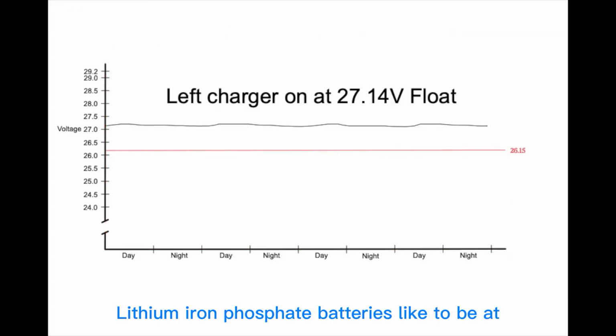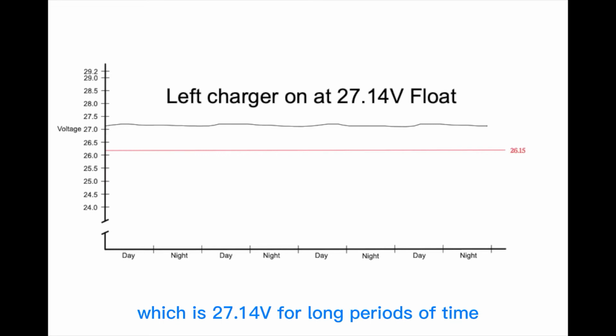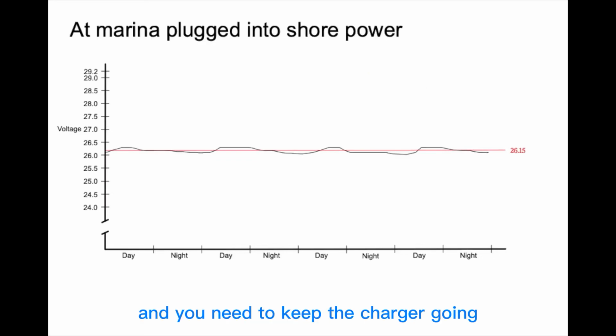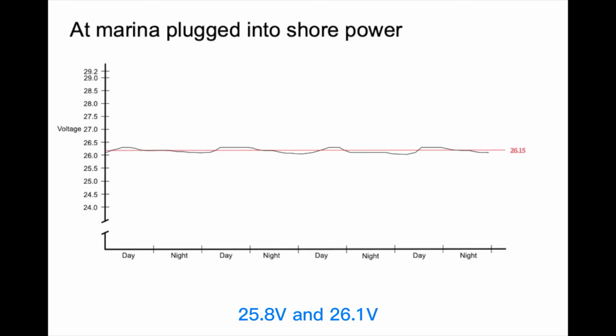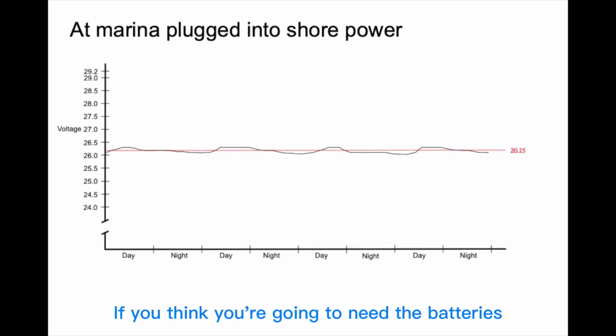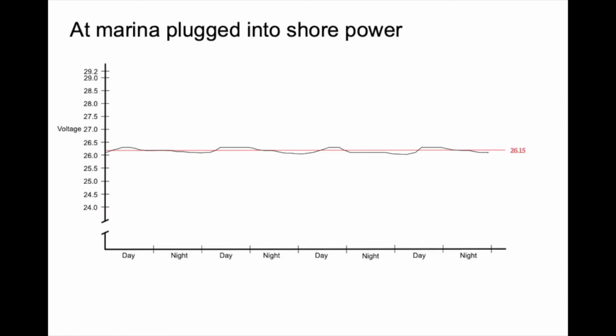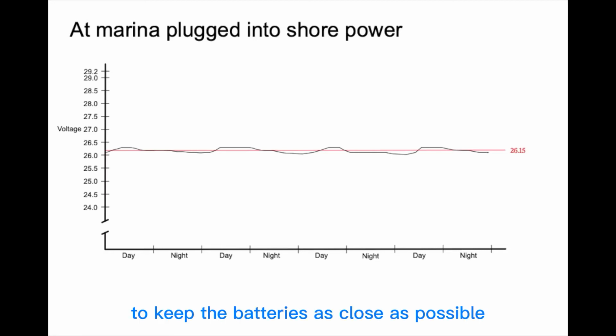Lithium iron phosphate batteries like to be at 50% capacity, so don't keep them at lead acid float voltage, which is 27.14 volts, for long periods of time. If you're in a marina and you need to keep the charger going, set the float voltage at a lower voltage, maybe between 25.8 volts and 26.1 volts. If you think you're going to need the batteries at night because of a power failure, set the voltage to 26.1. If not, set it lower. Adjust your float voltage for your usage to keep the batteries as close as possible to 50% capacity.